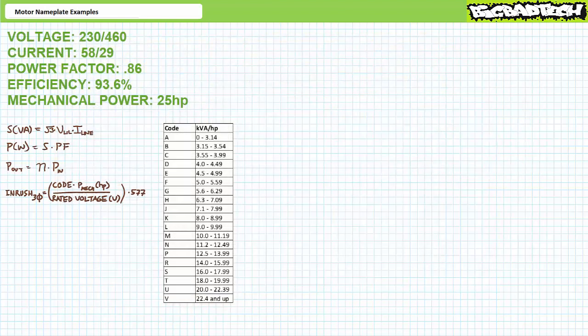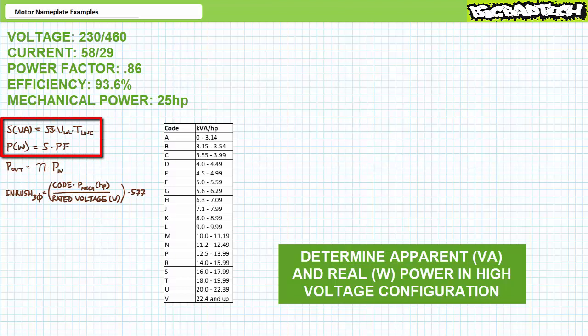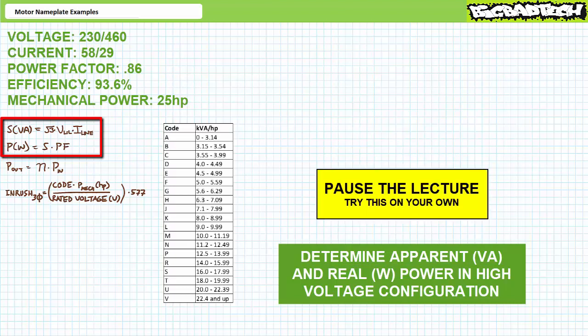While we've got the electrical data right in front of us, let's perform some basic electrical calculations. First, see if you can determine the apparent power in volt-amperes and real power input in watts drawn by this motor at rated condition — let's do so for the high voltage configuration. Apparent power in a three-phase AC system equals √3 times line-to-line voltage times line current. Real power input in watts equals apparent power times power factor. By all means, pause the lecture and try this on your own.